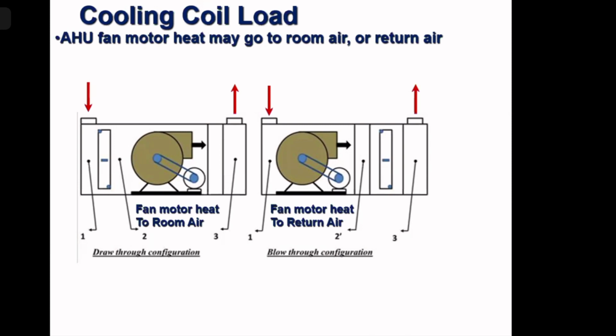So you must know what kind of cooling coil you are using. So better to use blow-through configuration of the cooling coil, because why unnecessarily taking the fan motor heat in the room air means it has to be taken out again by supplying some extra amount of cold air. That means it will increase my air handling unit fan capacity. So if there is no specific reason, better to use a blow-through configuration of air handling unit. Next.